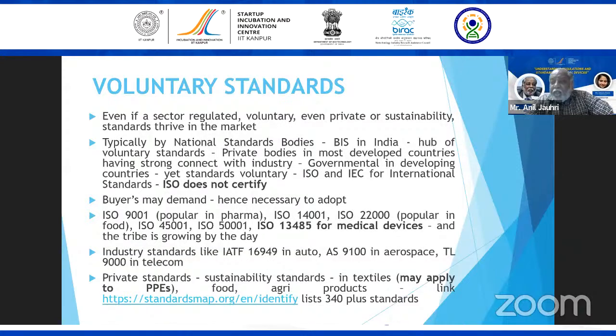You want to go to UK, you meet the UK regulation. If there is no buyer, what good is meeting the UK regulation? You need a buyer. And the buyer says, please show me a 13485 certificate. So even though you comply with Schedule 5, which is QMS, you still have to have an ISO 13485 certificate separately in case of medical devices. 9001 is very popular in pharma. The pharma industry goes for 9001, although there are regulations. 22000 is very popular in food, although there are regulations.